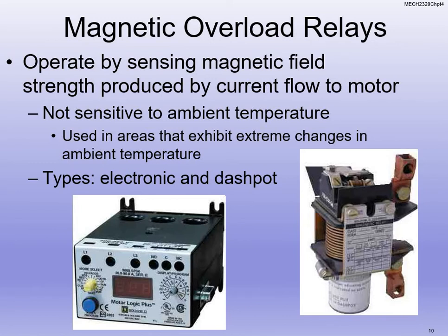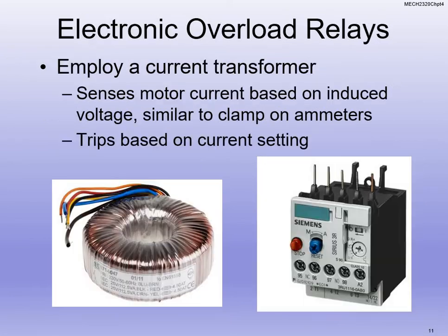So we can use the electronic and the dashpot methods, and we'll get into the dashpot piece here in a little bit. But we can also use a current transformer. It's really sensing the current based on the induced voltage. So we can detect what the voltage might be based on what the current value is, and you can change the sensitivity of whether it trips.